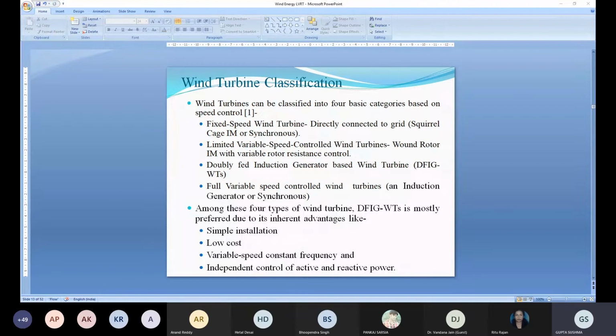But doubly fed induction generator based wind turbines are mostly preferred because they have many advantages: simple installation, low cost, variable speed, constant frequency. Because the wind turbine operates at a variable speed, if we are using the doubly fed induction generator, then we will have a fixed frequency output. This is the beauty of this DFIG, and that is why it is used widely at present. Also, independent control of active and reactive power. These are the advantages of doubly fed induction generator based wind turbines. So this is preferred.